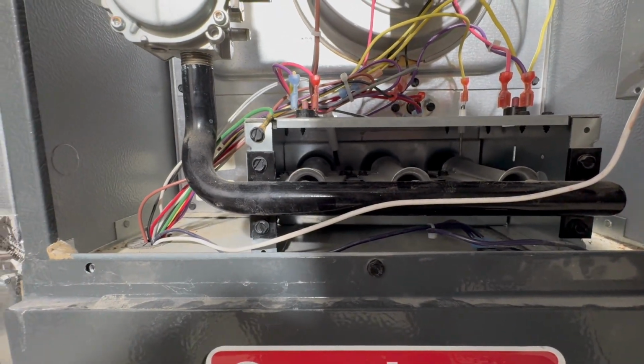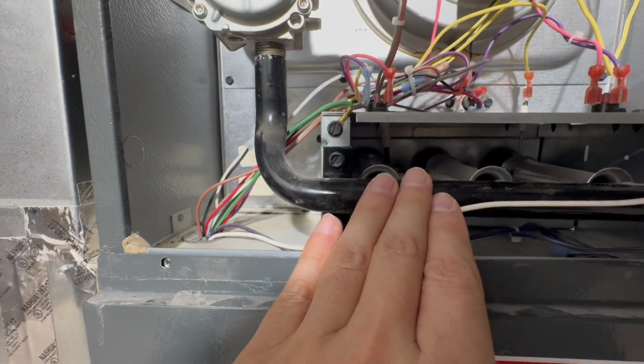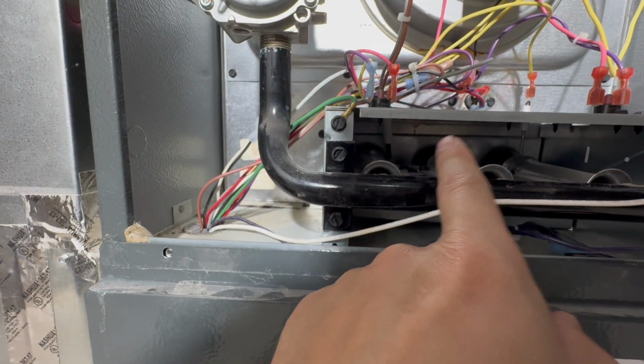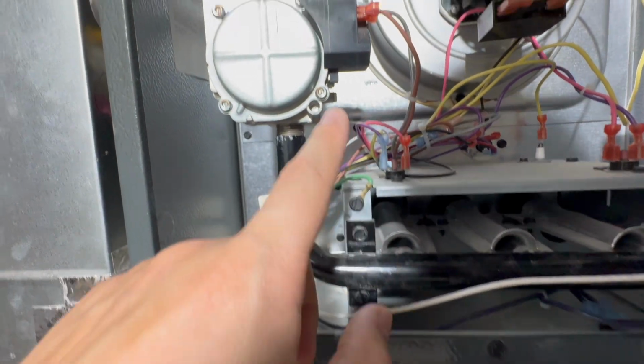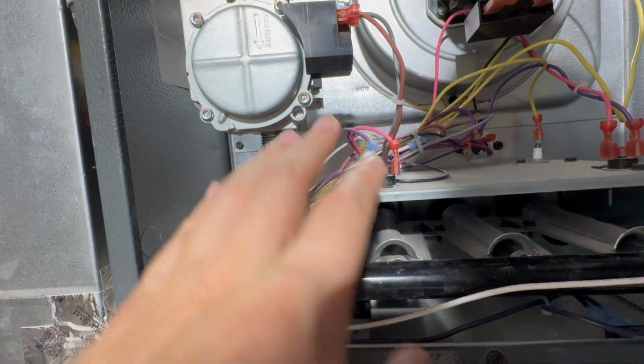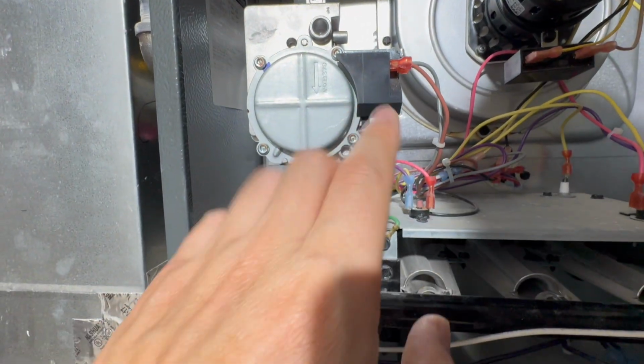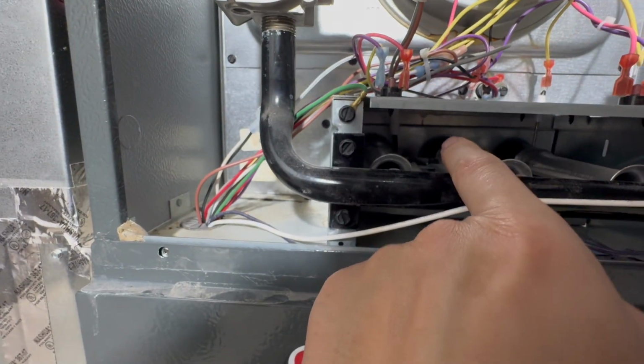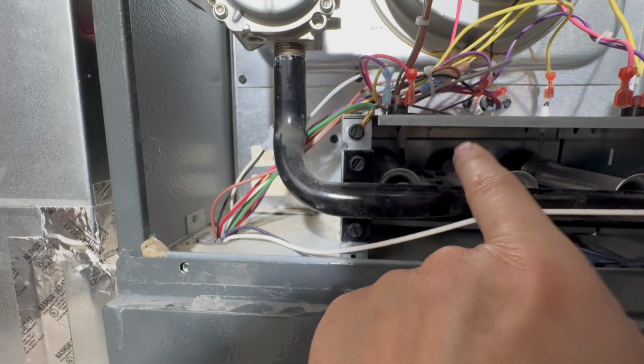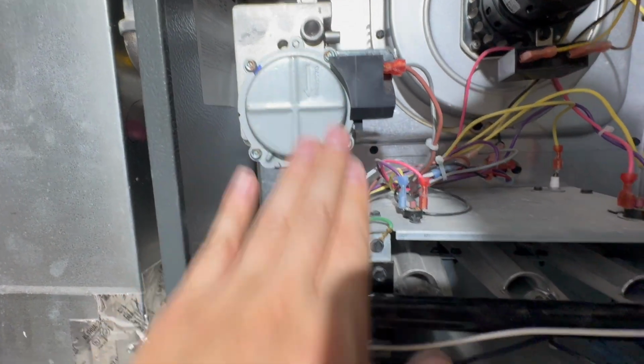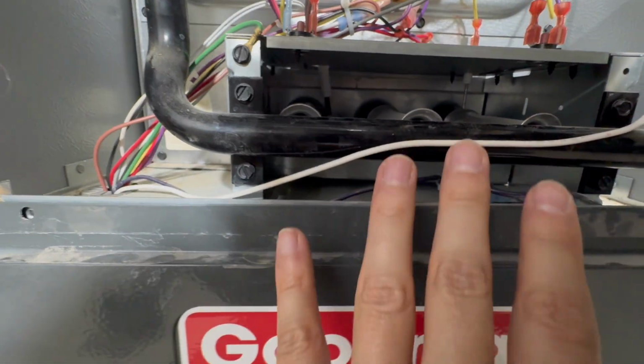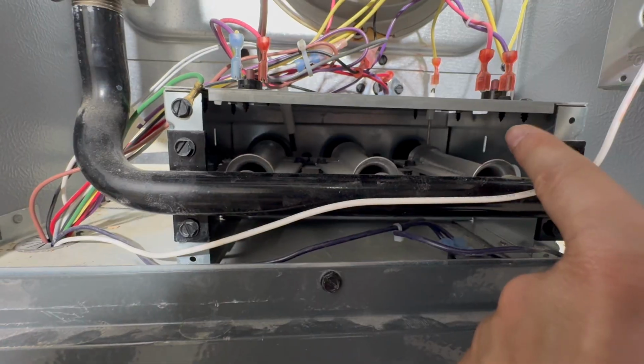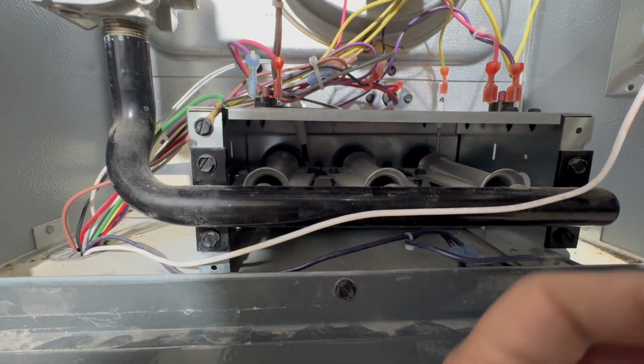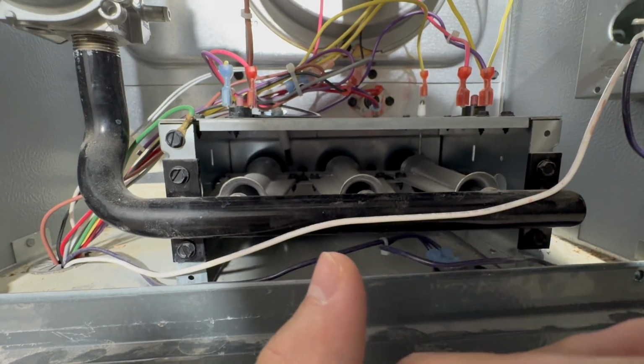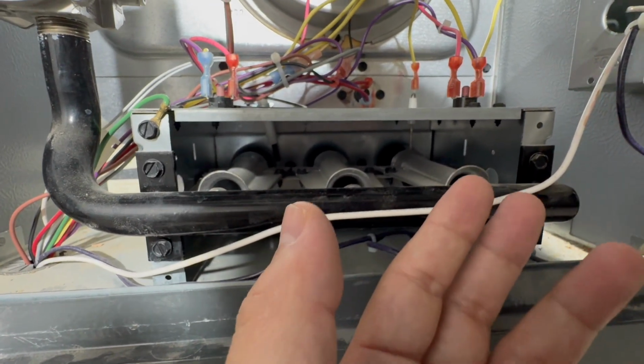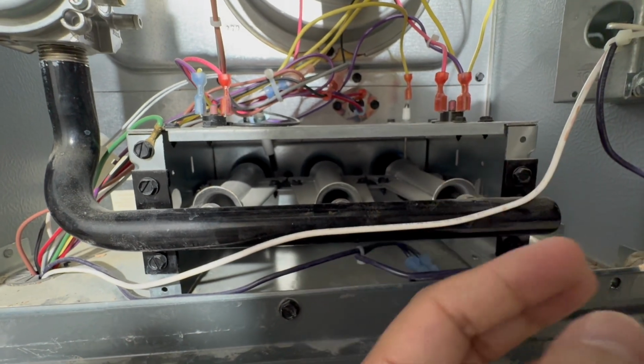And let's say you're getting the flame sensor, the igniter is on, everything is working fine, but you're not getting gas, so that means the valve is not good. But let's say you're getting the red igniter and the gas is blowing, but it's not staying constant, so that means the flame sensor is not working, because it's not sensing anything and it's saying that there's no heat. So that's why it's not keeping it constant.